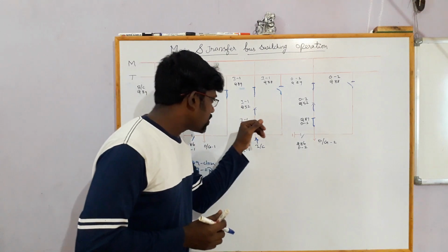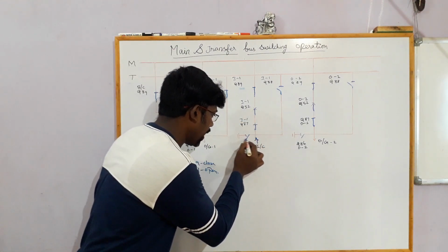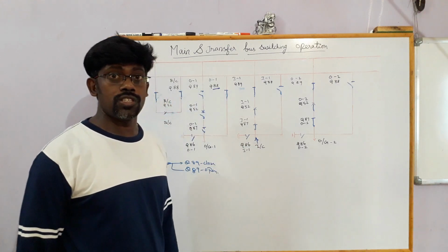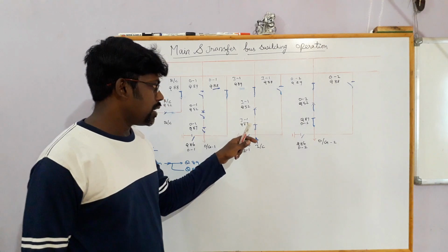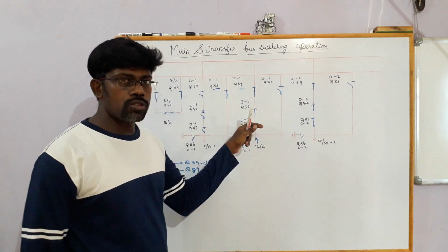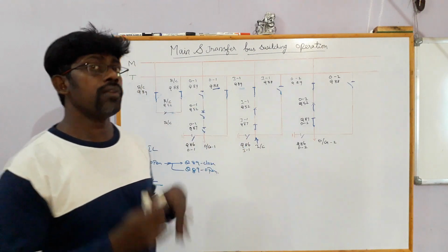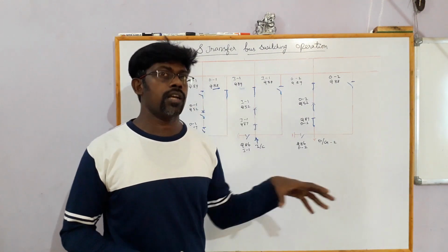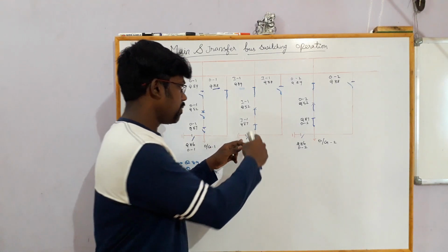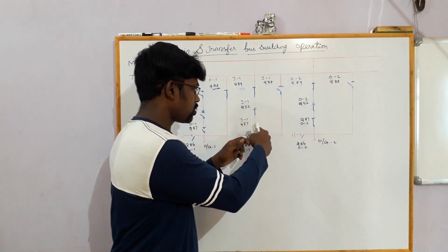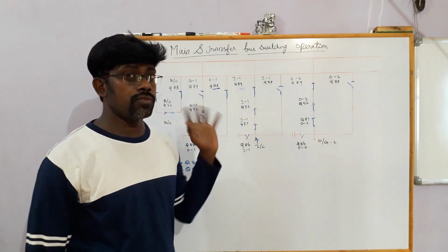If you see the Q87 interlock, beside this you have earth switch. If this earth switch is in close, whether we can close this 87? No, there will be a mechanical interlock. Anyway, we have to make it in electrical also. If both are in close, then the power is directly going to be in earth. So it is very dangerous.